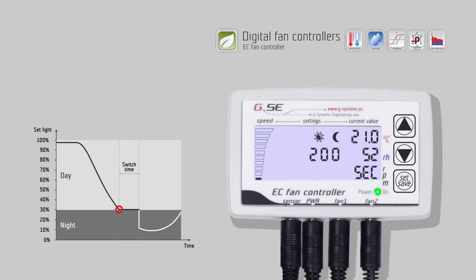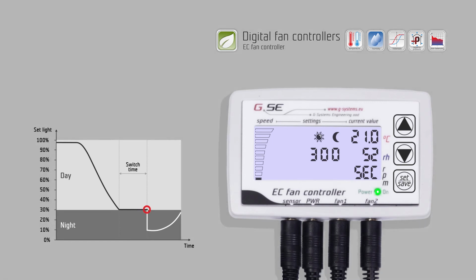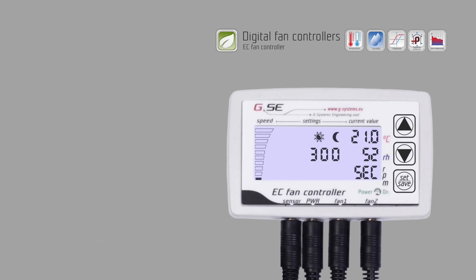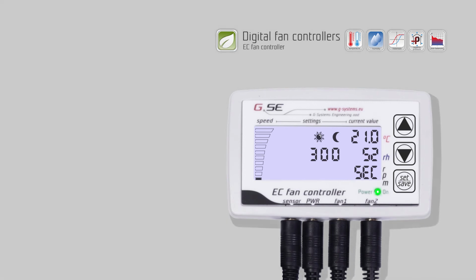Press down to go to the light sensor delay setting. This countdown is used to avoid an immediate switching between day and night mode, when the light sensor has reached the switching level. For example, we set the value to 300 seconds. When the countdown ends, assuming it doesn't get interrupted by getting light at the light sensor, the controller will switch from day to night time. In reverse, the controller will switch from night to day the same way.